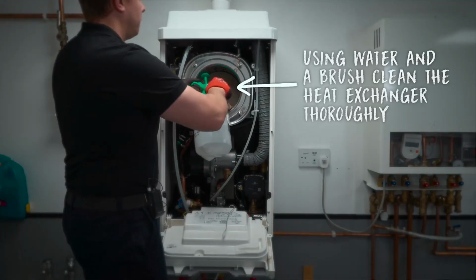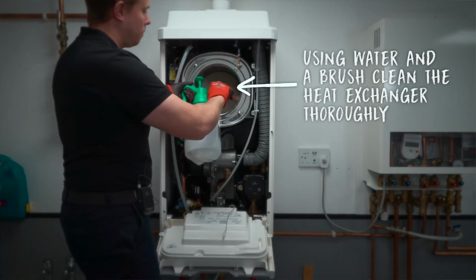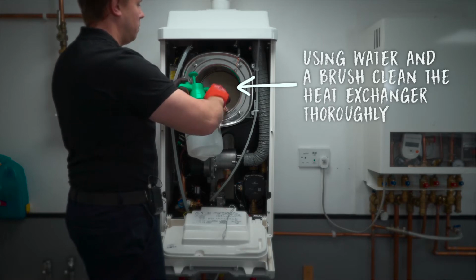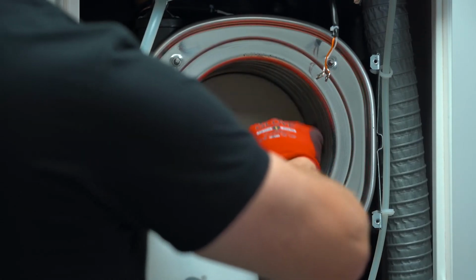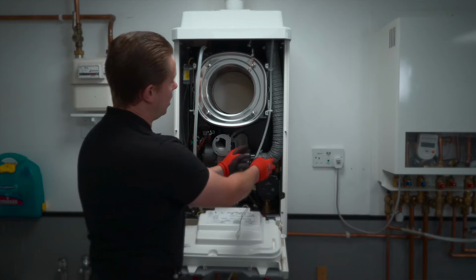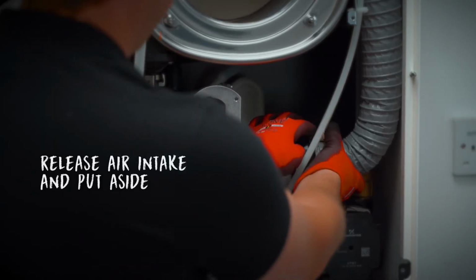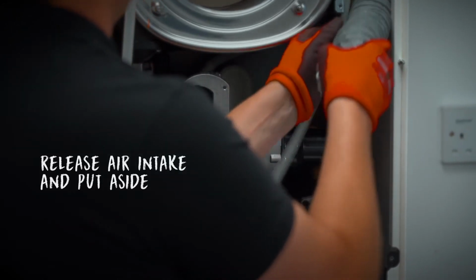Remove any deposits from the heat exchanger coils and then, using water, thoroughly clean the heat exchanger. Any water used will drain away through the condensate trap. Next, release the air intake and put it to one side.